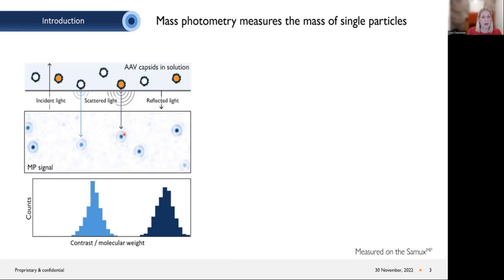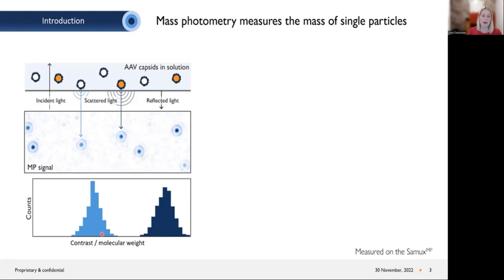Basically, we look at the interference of scattered light and reflected light, which gives us interference patterns. Every single dot visible on the camera chip corresponds to a single molecule — a single AAV molecule in this case. The intensity of the contrast inside each dot relates to the amount of scattering and therefore to the mass. We analyze the contrast inside these dots, and the result is initially counts over contrast. You can then calibrate the system with one known protein; for AAVs, you can use empty AAVs, and the output is a histogram with counts over molecular weight.